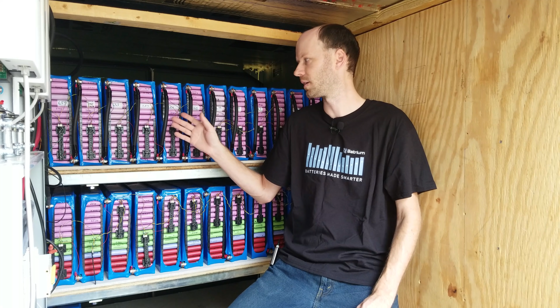They have been improved significantly since the Watchmon 1, now using much thicker, harder wiring, and the connectors are soldered on and crimped better. But the core problem still exists where they used a very tiny version of the JST connector instead of the standard size. The more times you play with these wires, the connectors tend to break and the wires pull out. In fairness, this system is designed to install and not touch, whereas I'm constantly tinkering with it, so that's not necessarily a fault of Batrium.